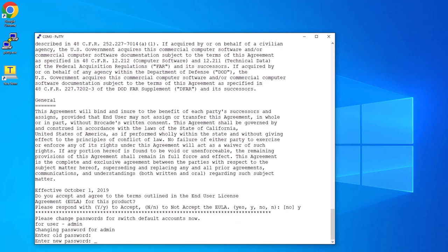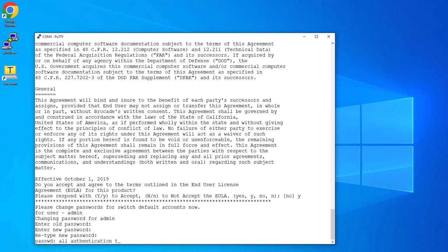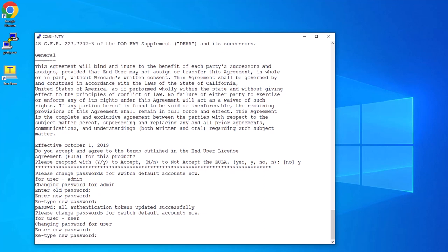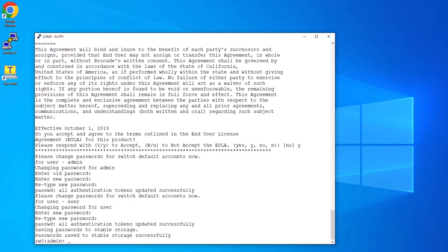Next, you'll be prompted to change the default password for the default admin account. After that, you'll be prompted to change the default password for the user account. Once you're logged in, you're ready to set the IP address for the switch. The command to configure the IP settings is ipaddrset.